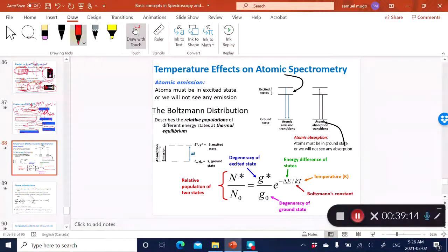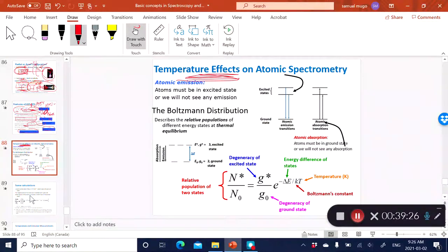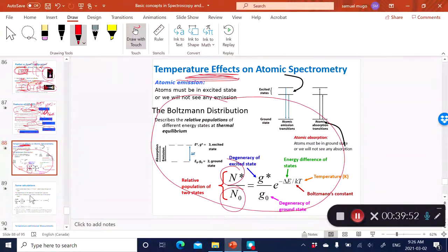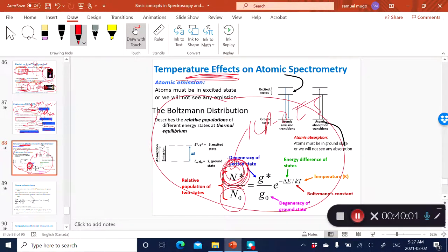It's important to remember that you need the ICP temperature to be very stable because it affects your signal. You're totally dependent on temperature stability for good precision. This is based on the Boltzmann distribution, which describes the relative proportion of atoms present in the ground state versus the excited state. For ICP-OES, you want the majority of atoms in an excited state, whereas for atomic absorption spectroscopy, you want the majority of atoms in the ground state.